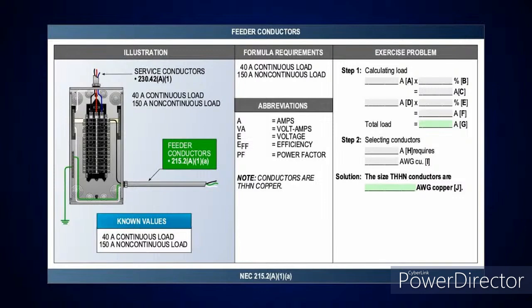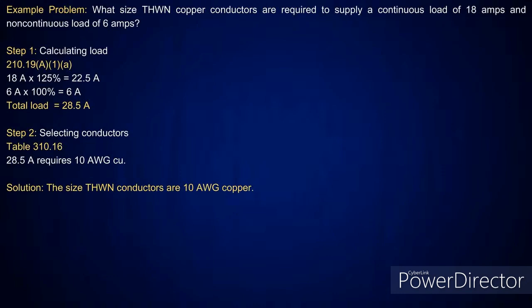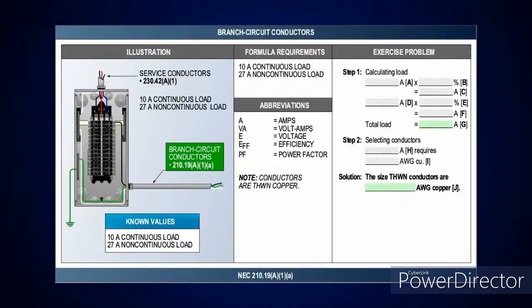For this illustration: 40 amps continuous, 150 amps non-continuous — take continuous at 125%, non-continuous at 100%, add it all up, then go to Table 310.16 at 75°C and select your conductor size. Here's a branch circuit: 18 amps continuous, 6 amps non-continuous. Per NEC 210.19 A1A, continuous at 125% gives 22.5 amps, plus 6 amps non-continuous at 100% — total 28.5 amps. Go to Table 310.16, next amperage above that is 30 amps, come across: you need a number 10. Did I change the calculation going from a service to a feeder to a branch circuit? No. The calculation is the same — just different code sections.